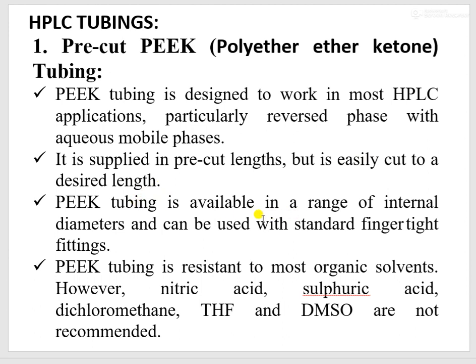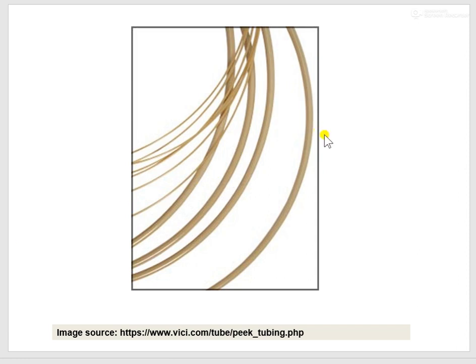PEEK tubing is resistant to most organic solvents. However, nitric acid, sulfuric acid, dichloromethane, THF, and DMSO are not recommended with PEEK tubing.